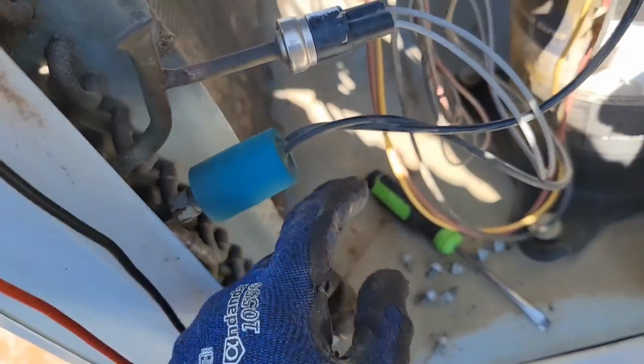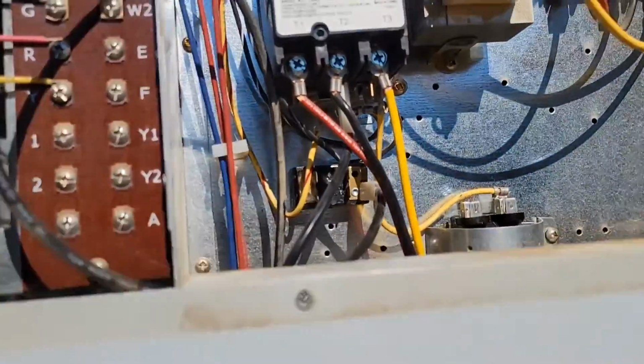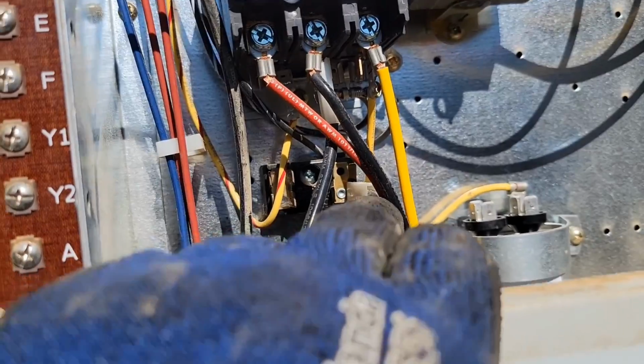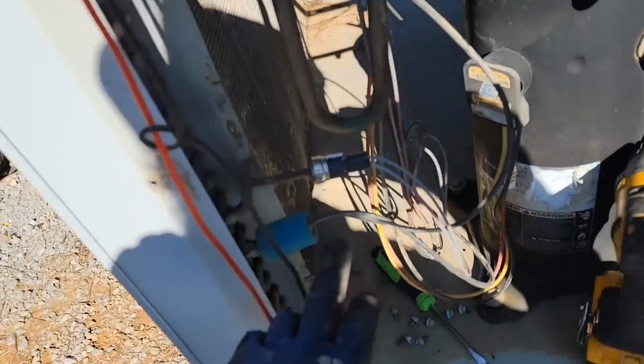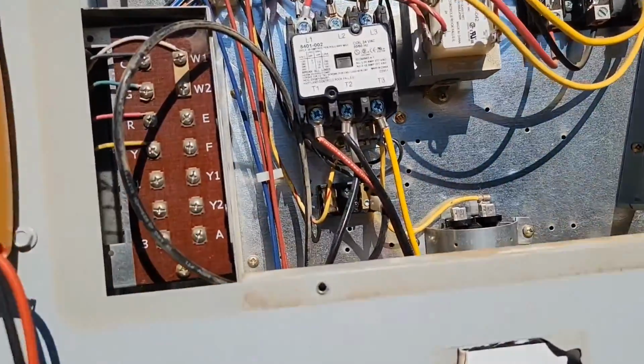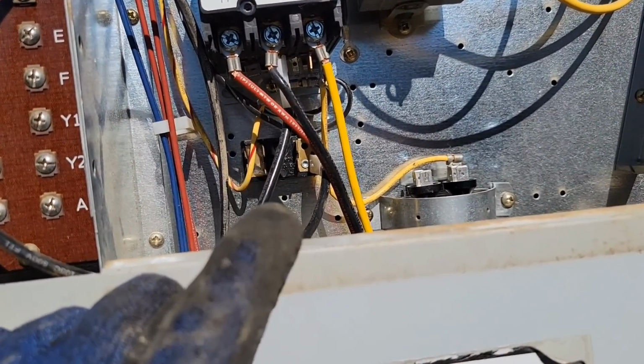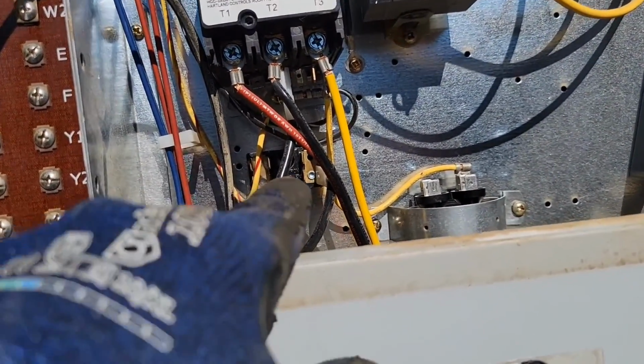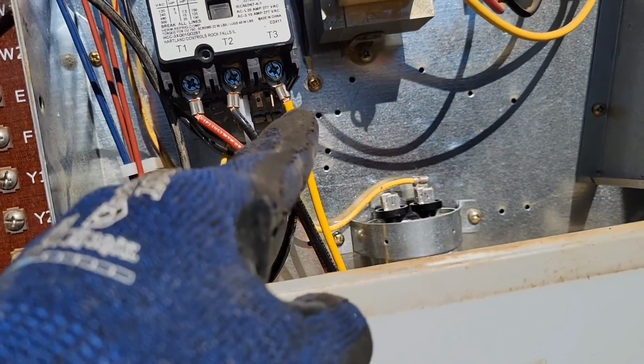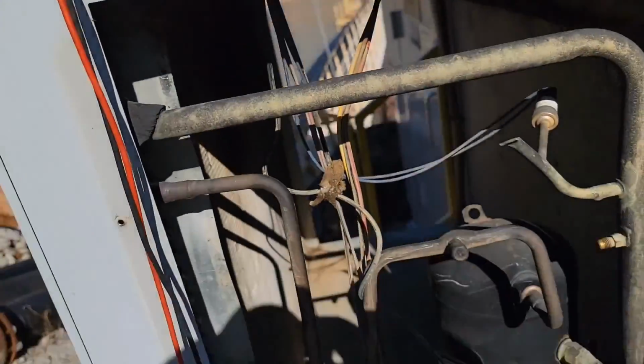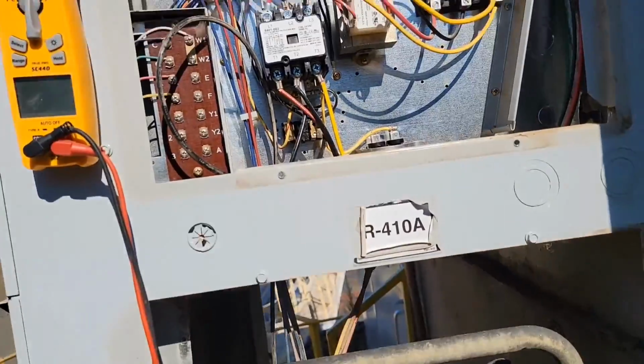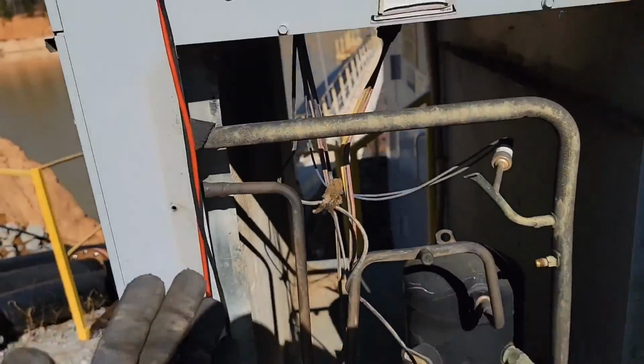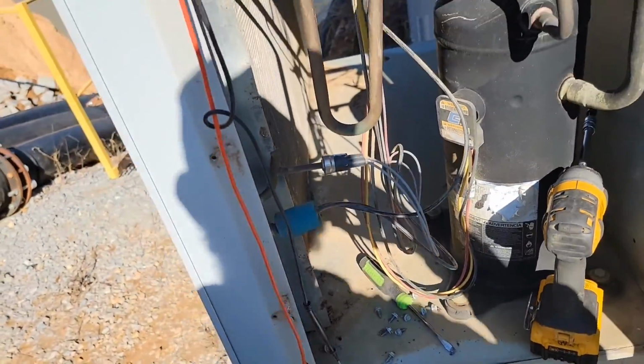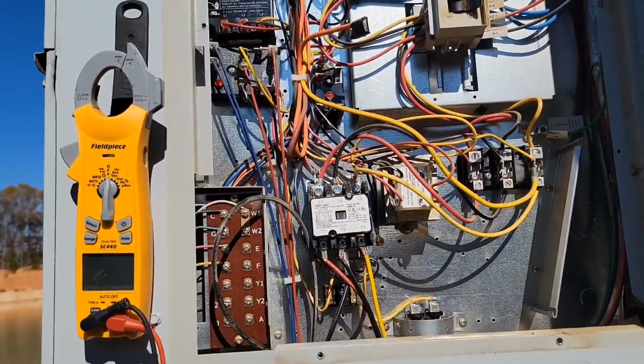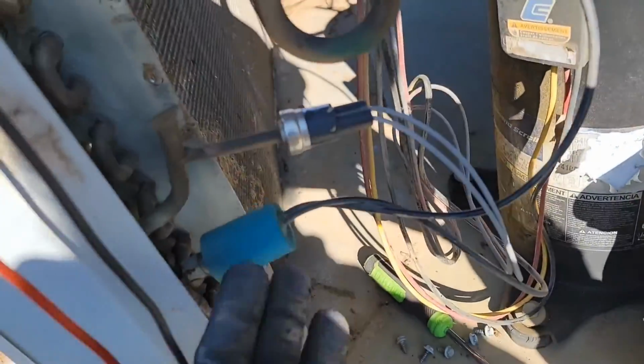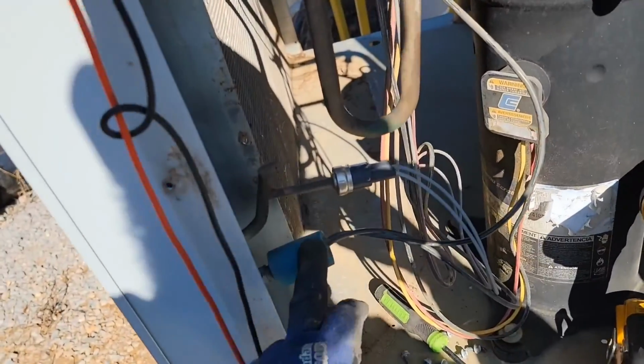It goes down, it goes into the pressure switch, and then it comes back out, and that's what powers that fan. So if the pressure switch is not closing, then it can keep that fan from having the power that it needs. Now, I verified power, so I actually checked from this terminal to T3, and my pressure switch is closed. So we got power, but I wanted you to know that, because if you don't know that, then you're gonna change a motor for nothing, and your motor might not be bad. It might be the pressure switch, okay? And pressure switches go bad.